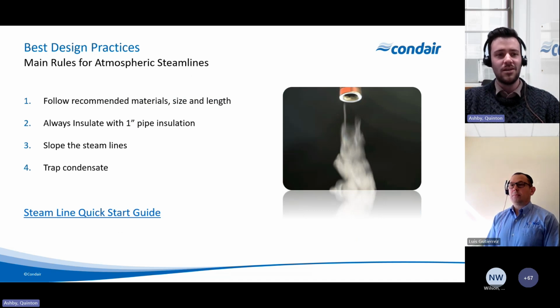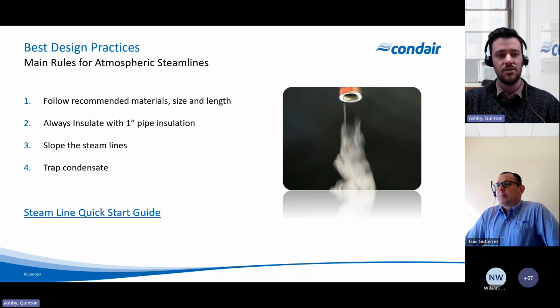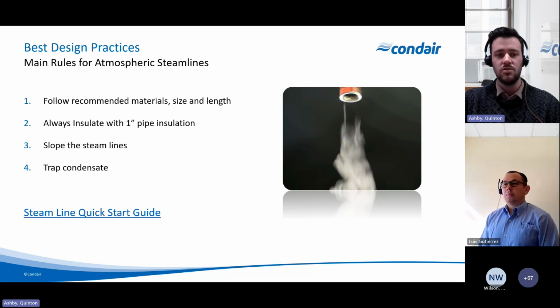So for today, we kind of just wanted to cover some best design practices because we see a lot of issues in the field of people not fully understanding atmospheric systems. So a lot of people seem to think that atmospheric steam lines are the same as pressurized. They actually have completely separate rules for how we install them. So just some general guidelines: we always want to follow recommended materials, size, and length. We have those out in our installation manuals, and those should always be followed. Otherwise, there can be some issues in terms of back pressure to the units, which can cause faults.